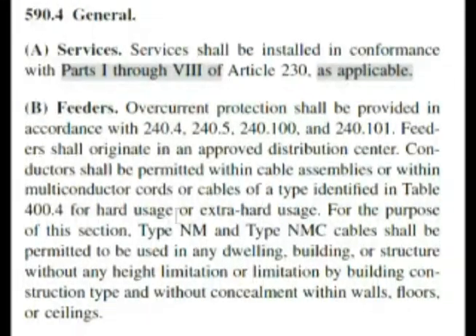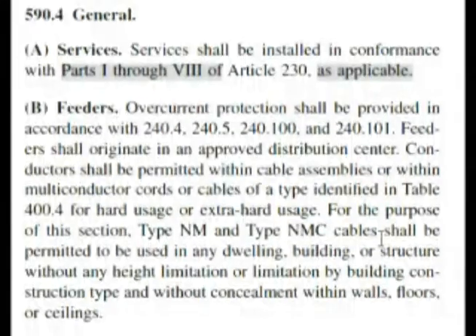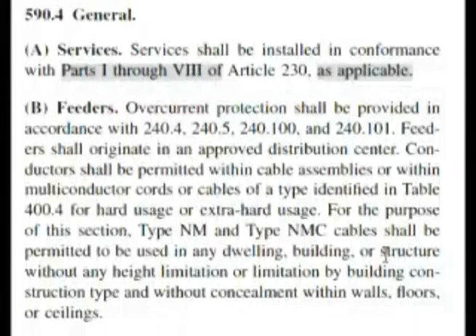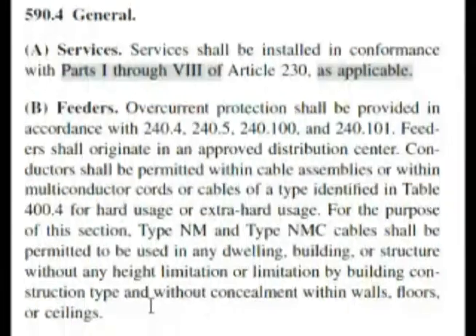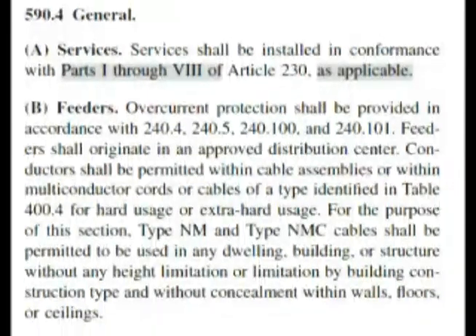If you look at it, Type NM kind of jumps out of the paragraph at you. It says it shall be permitted to be used in any dwelling, building, or structure without any height limitation or limitation by building construction type, and without concealment within walls or ceilings. Our question asks if it can be used, and the code says that it can without height limitation. So this makes the answer A — true — for our test.